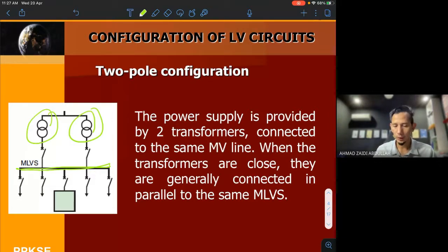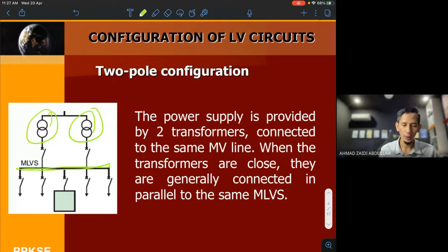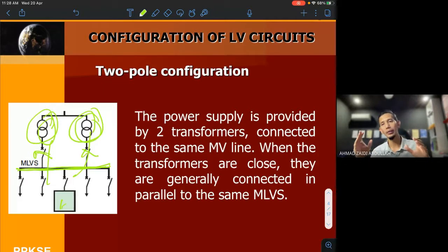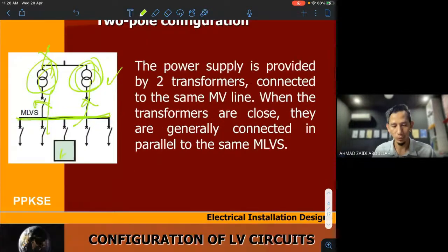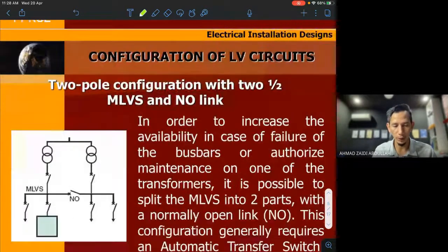When the transformers are closed, they are generally connected in parallel to the same supply. Bila dia close, this one closes and this one also closes, so they are connected to the same supply in parallel lah. So this load can take supply from this transformer, also from this one. So good lah. I can have two supplies, kan? Maybe this one trips, so it can still use the other transformer. So the system will stay operating lah.